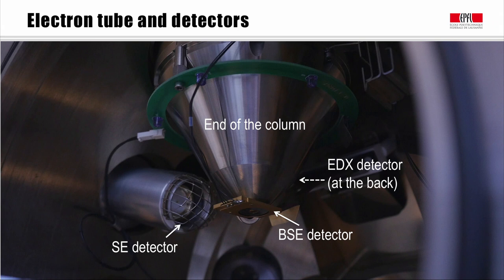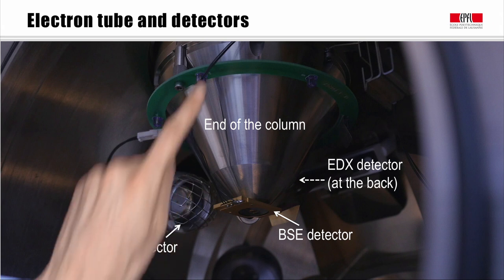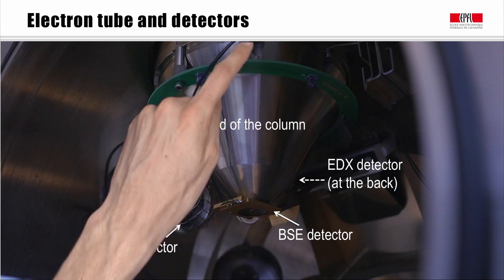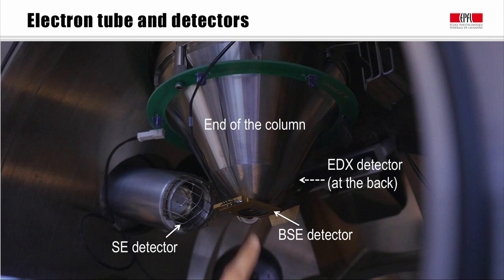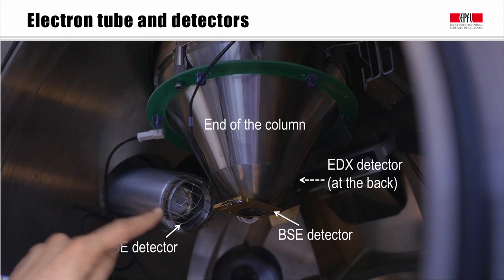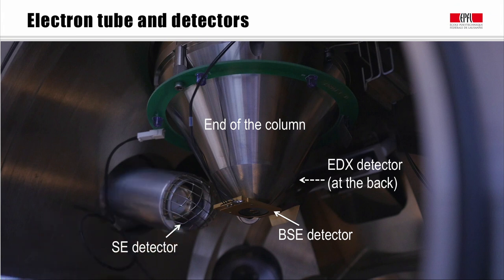This image shows how the chamber of the microscope looks. You have the end of the column here — the incident beam comes through this hole to the chamber, with the sample holder right below. Electrons are sent to the sample, and all these interactions are collected by different detectors: the secondary electron detector with the grid on top, the golden plate which is the BSE detector, and the EDX detector at the back. All this information can be collected in one microscope.